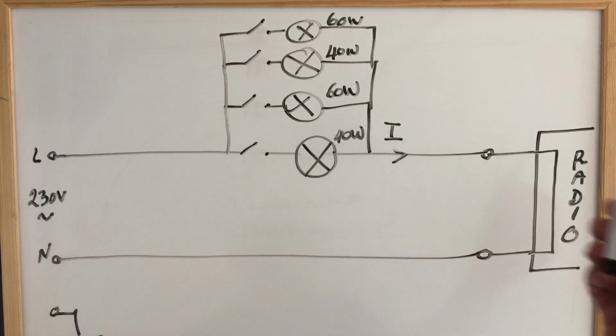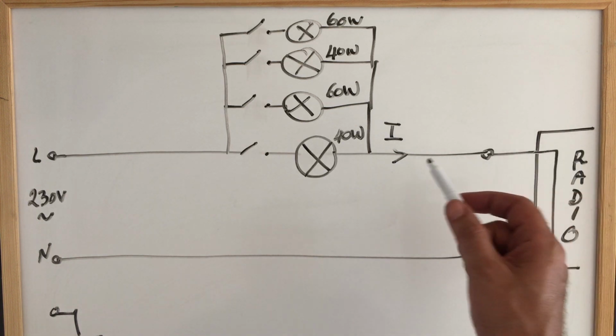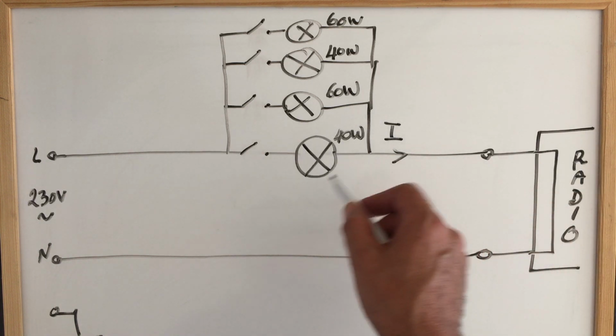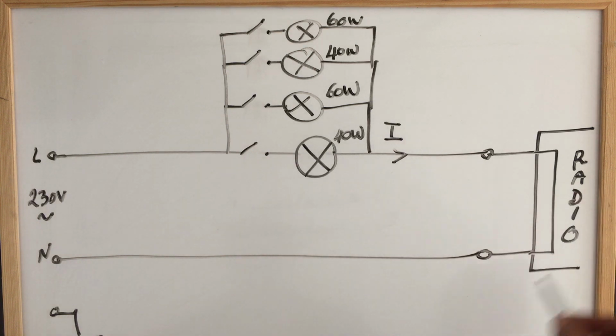So I would only switch that one in. Then my current is limited to, let's see, 230 volts through a 40 watt light bulb, about 1/6 of an amp, about 170 milliamps or so. That would be the maximum current that could go through that damaged radio, if it were damaged.